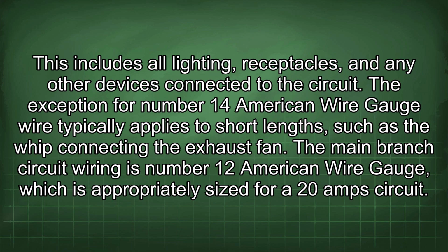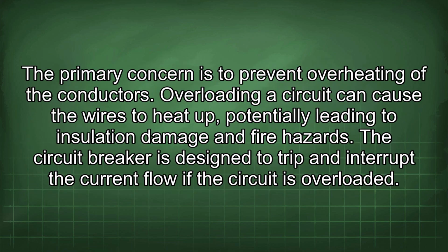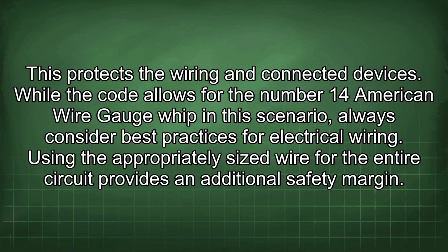The exception for number 14 American wire gauge wire typically applies to short lengths such as the whip connecting the exhaust fan. The main branch circuit wiring is number 12 American wire gauge, which is appropriately sized for a 20 amp circuit. The primary concern is to prevent overheating of the conductors. Overloading a circuit can cause the wires to heat up, potentially leading to insulation damage and fire hazards. The circuit breaker is designed to trip and interrupt the current flow if the circuit is overloaded. This protects the wiring and connected devices.